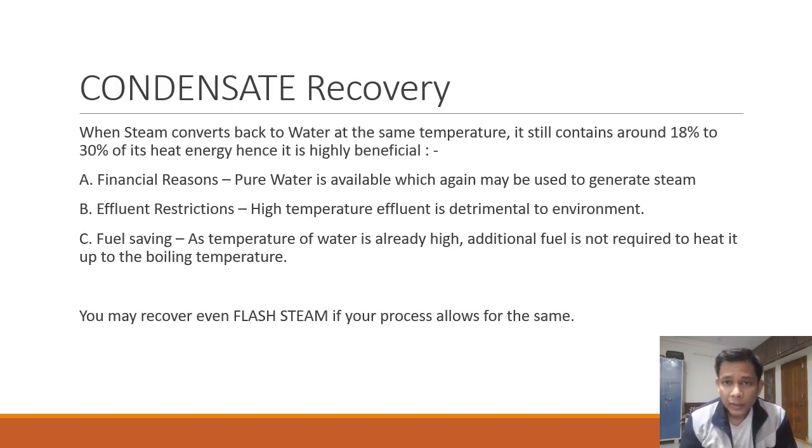Now, after the steam is utilized, condensate is formed, but what to do with the condensate? You can throw it away, but it is not advisable. What should be your strategy? You see, when the steam is converted back to its water phase by transfer of heat, it still contains around 18% to 30% of its heat energy.